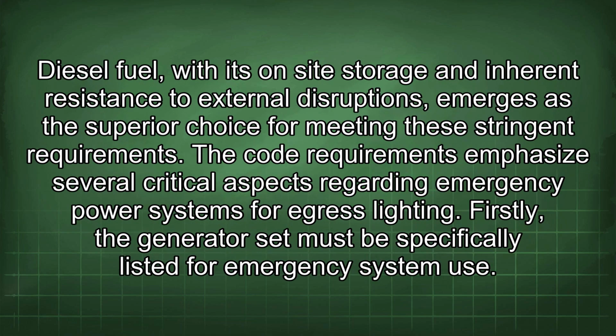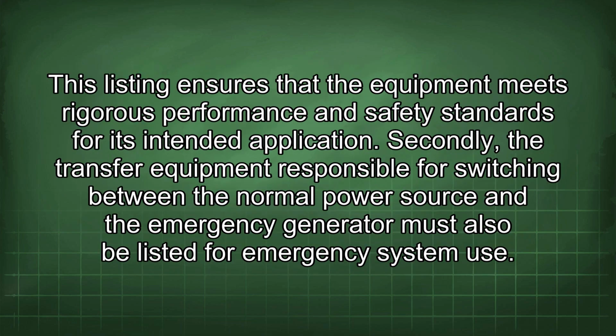Diesel fuel, with its on-site storage and inherent resistance to external disruptions, emerges as the superior choice for meeting these stringent requirements. The code requirements emphasize several critical aspects regarding emergency power systems for egress lighting. Firstly, the generator set must be specifically listed for emergency system use. This listing ensures that the equipment meets rigorous performance and safety standards for its intended application.